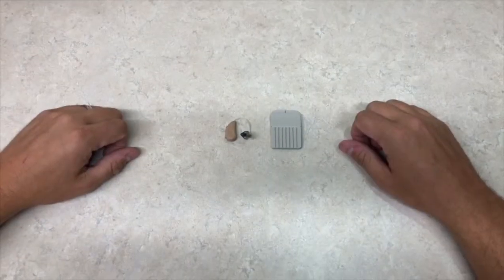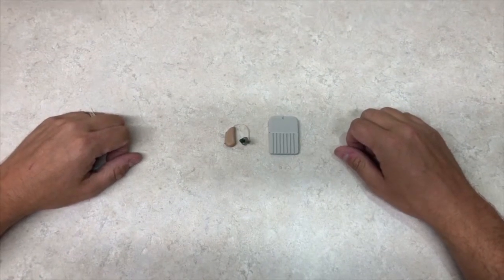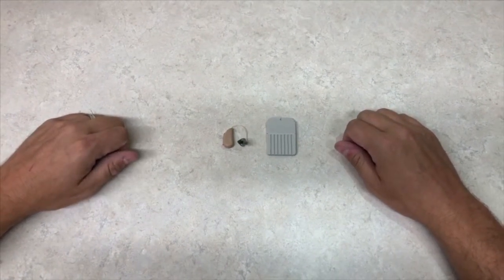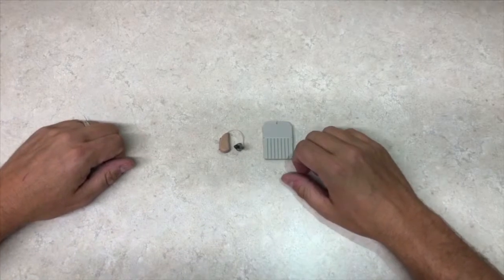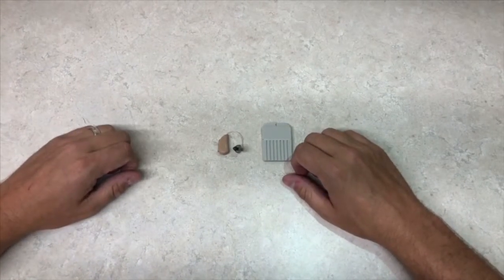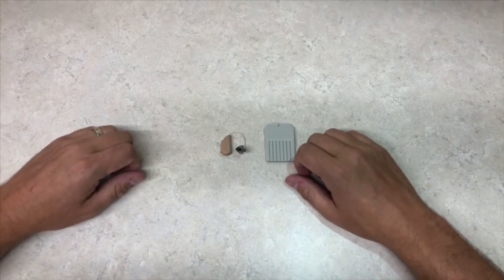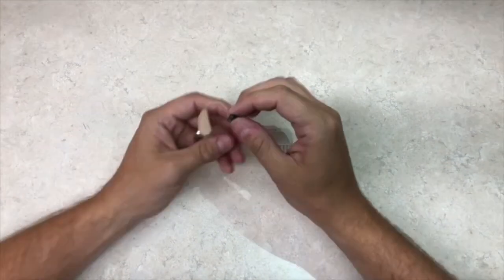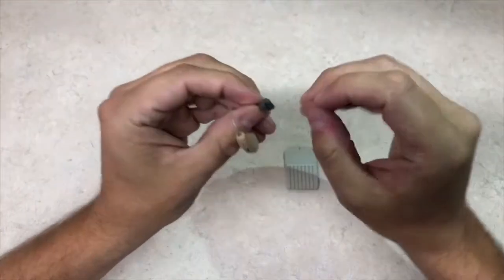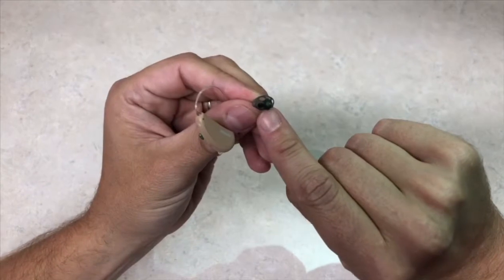One of the most common reasons that hearing aids don't work, aside from the battery being dead, is they get plugged with earwax. So today we're going to change the wax trap on a RITE, or receiver in the ear, hearing aid. In order to change the wax traps, you're going to remove the little rubber tip at the end.